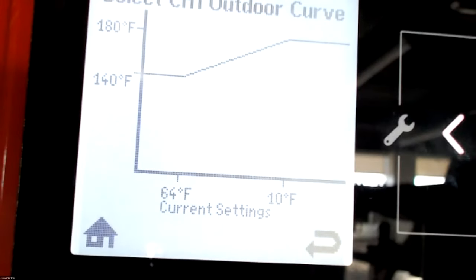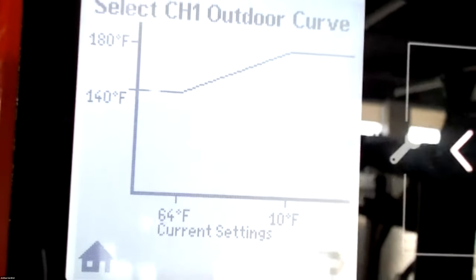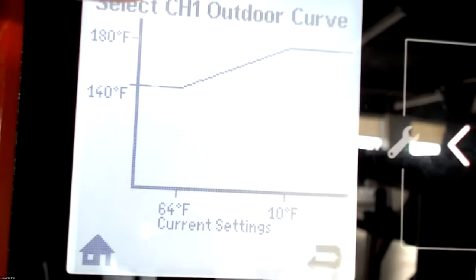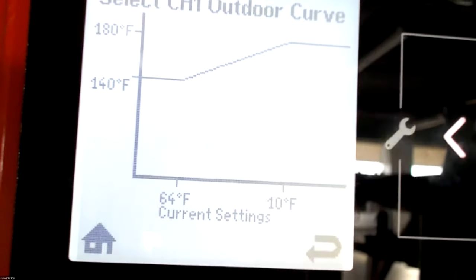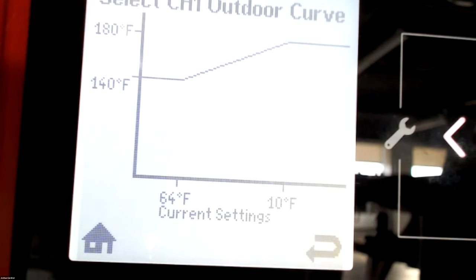The first thing it's going to have is select CH1 outdoor curve. That's going to be in the top. And then we're going to show a graph. So this is nice because it shows us what the outdoor reset is set for, where a curve is. Now, this is where a lot of guys get confused and we have a lot of issues. So we made these preset outdoor curves to make it a little bit easier. But in most cases, I want to adjust a few of these temperatures in the back end. We have some quick ones in here.